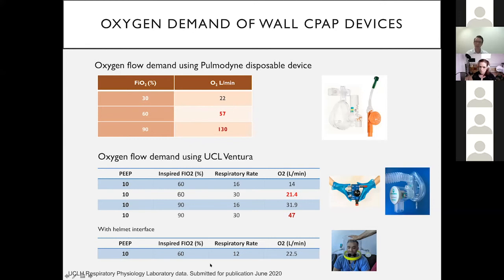I'd also mention that using the helmet, which was favored in many Italian hospitals, the oxygen demand is also reasonable. One caveat, though: it's important to pay attention to the flow necessary when setting the UCL Ventura up, such that the flow should be decreased to that required to provide the PEEP within the device.